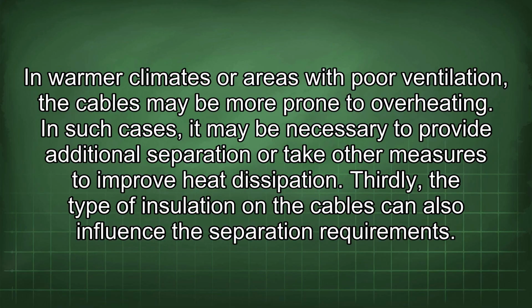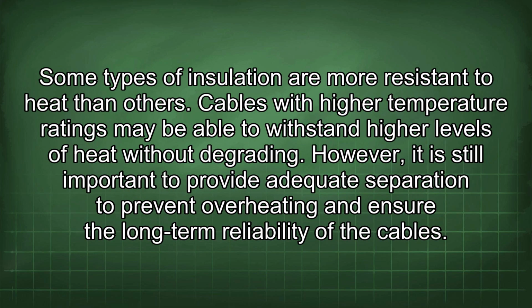Thirdly, the type of insulation on the cables can also influence the separation requirements. Some types of insulation are more resistant to heat than others. Cables with high temperature ratings may be able to withstand higher levels of heat without degrading. However, it is still important to provide adequate separation to prevent overheating and ensure the long-term reliability of the cables.